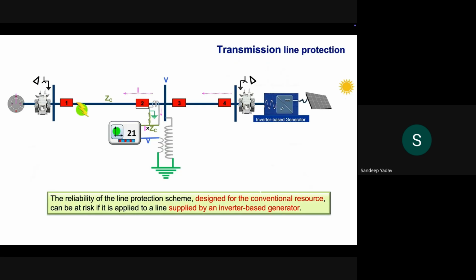So with this, when it comes to the reliability of the protection, all these protections, be it differential, ground fault protection, distance protection, or the impedance protection, all of these have been designed keeping the behavior of synchronous generators or the conventional sources in mind. So what would be the phase relationship between voltage and current when it feeds an inductive fault, a highly resistive fault? All those behaviors have defined and formulated the very basics of our protection algorithm in the conventional impedance relays or our distance relays.